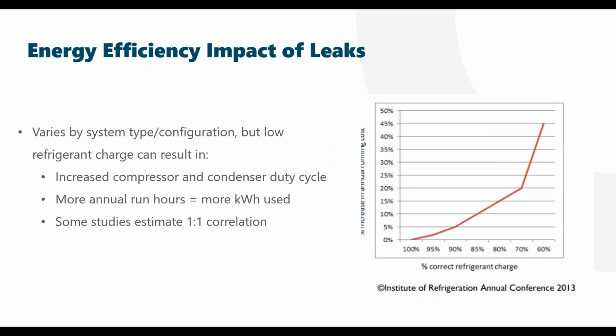So, energy efficiency impact of leaks. I tried to keep this slide somewhat vague because the energy efficiency impact of refrigerant leaks on system performance is very variable, and it's something a lot of people are still working to figure out how to quantify. It varies by system type and configuration, but low refrigerant charge at a high level can result in increased compressor and condenser duty cycle. You have less refrigerant capacity, so your refrigeration system components are running more to provide the same cooling benefit. Longer run hours means more kWh used on your system. There are some studies that estimate a 1-to-1 correlation, so 1% refrigerant leak is equivalent to a 1% efficiency hit on your refrigeration system.